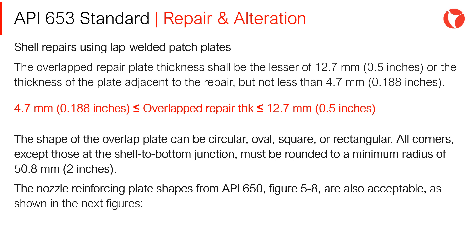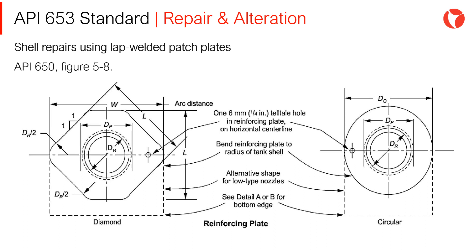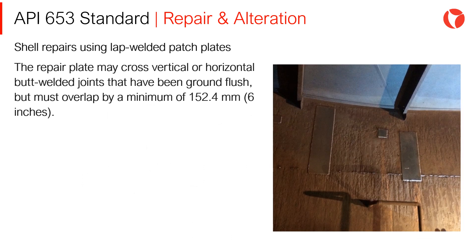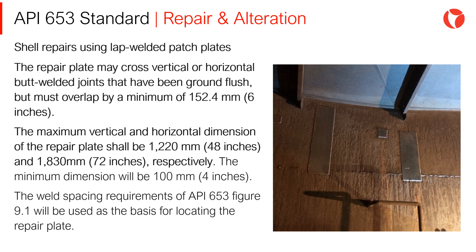The diamond shape shown on the left is an acceptable form for reinforcing plates. The repair plate may cross vertical or horizontal butt-welded joints that have been ground flush, but must overlap by a minimum of 152.4 mm. The maximum vertical and horizontal dimensions of repair plates shall be 1220 mm and 1830 mm respectively. The minimum dimension will be 100 mm (4 inches). The weld spacing requirements of API 653 figure 9.1 will be used as the basis for locating the repair plate.